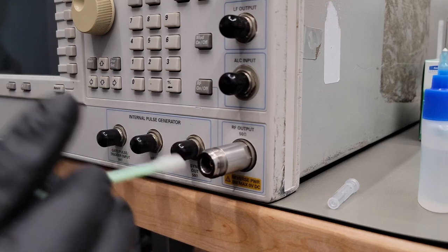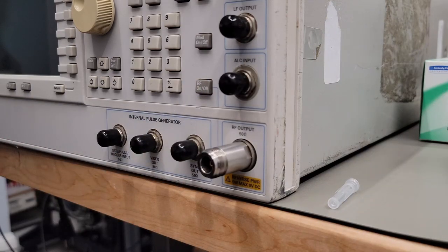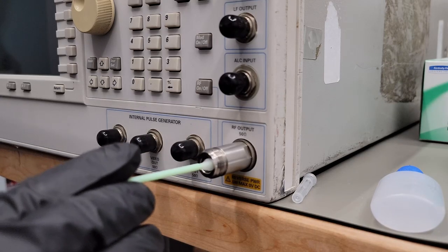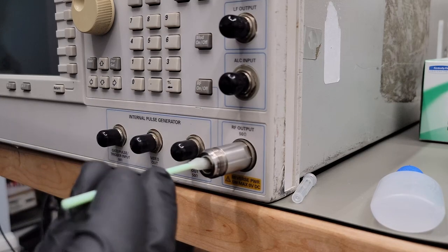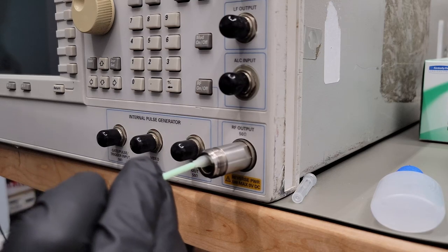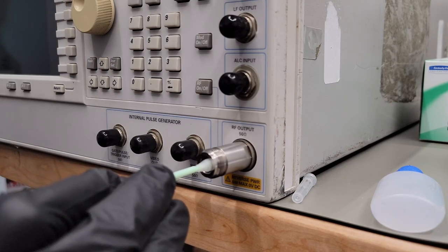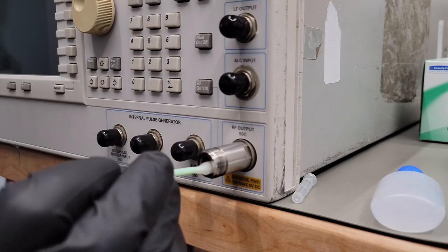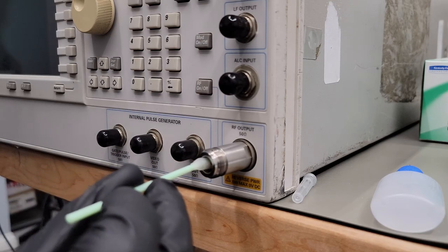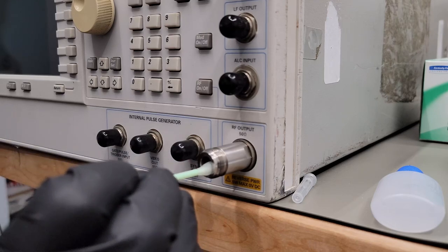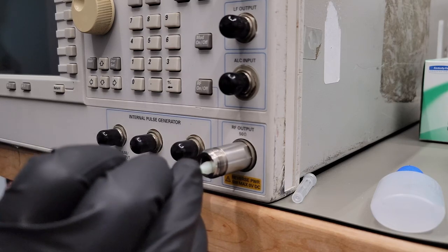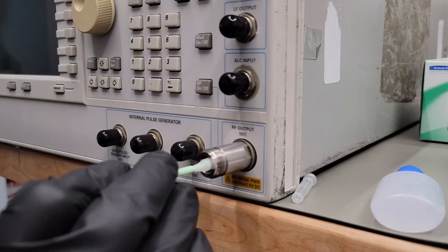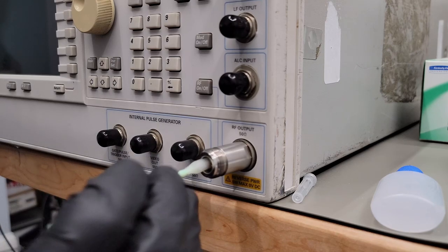So you don't want to go ahead and jam this in there aggressively. Just be very careful. You know, don't over insert the foam swab. Just swab up onto the inner. There actually is an inner shelf in this conductor, which is before the center conductor support. And that's where I'm stopping. So I don't need to jam this all the way in there. And you really just need to clean that part of the connector because that's where the microwave interface really is between the center conductor and the inside of the outer conductor here.